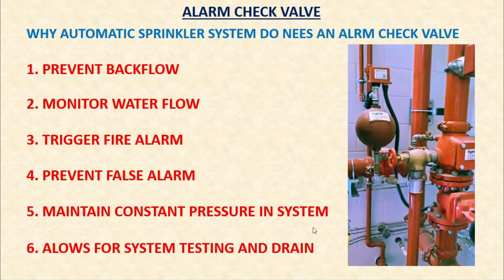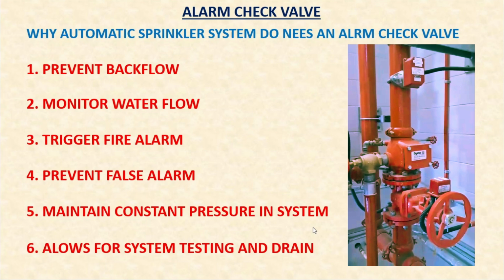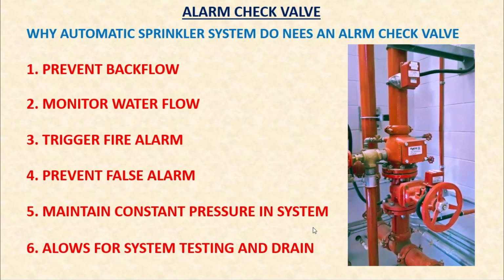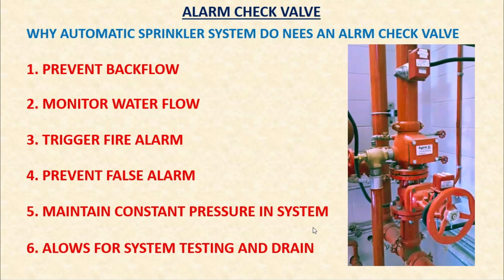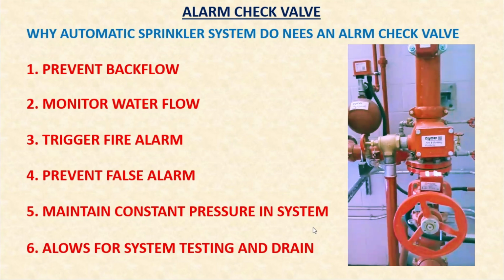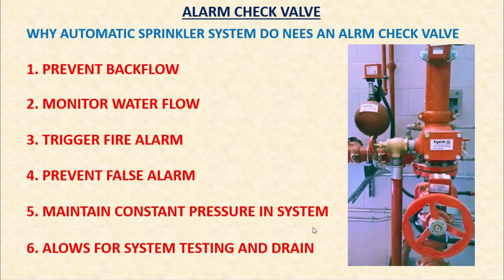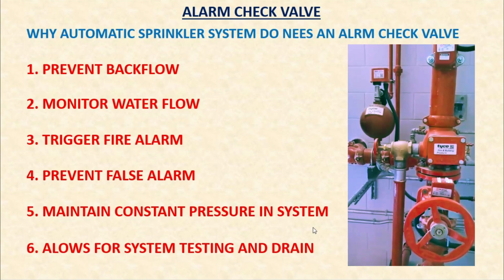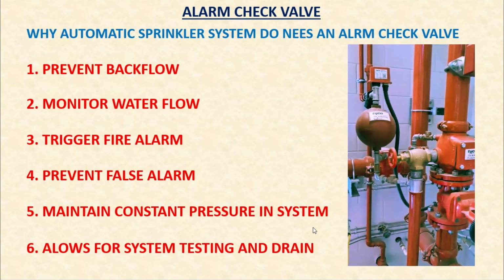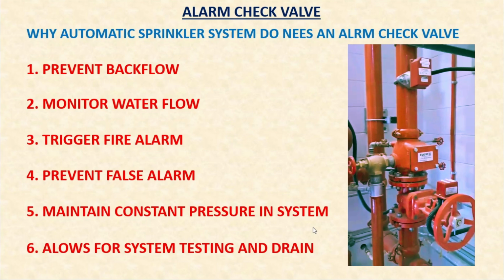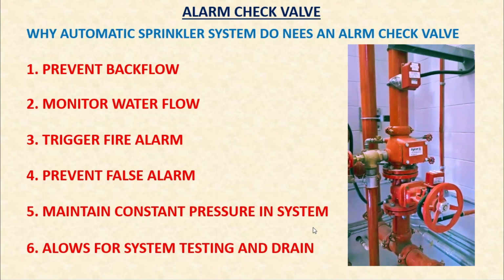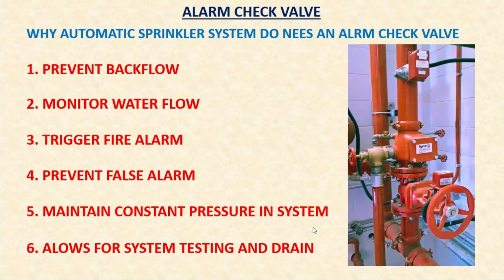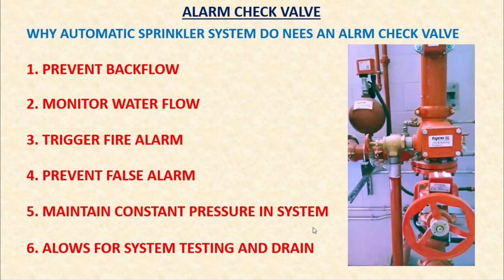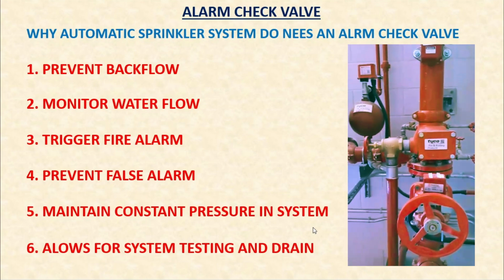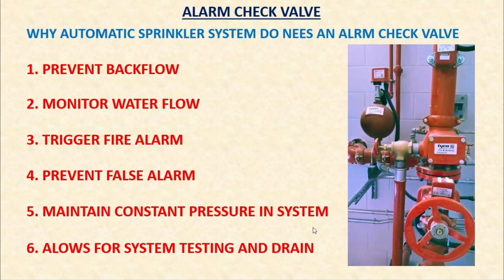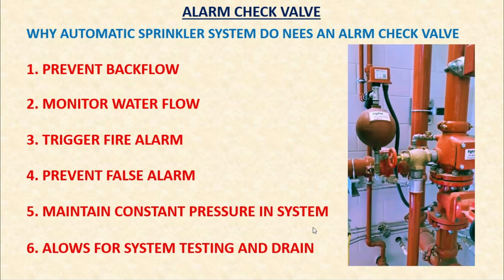So we have seen alarm check valve components. Now let us see, why do we need an alarm check valve in a sprinkler system? What will happen if the alarm check valve is not there? So the first thing it does is to prevent backflow. The alarm check valve prevents water from flowing back into the main water supply after entering into the sprinkler system. Otherwise, in the absence of an alarm check valve, all water will be drained either to the water supply tank or outside. Next thing is it monitors water flow.